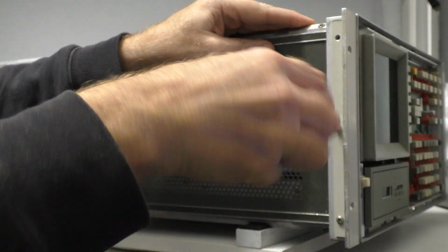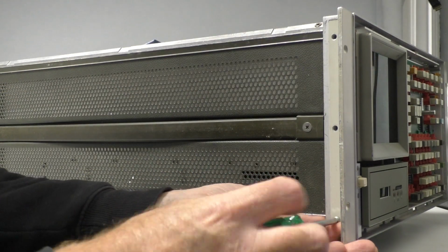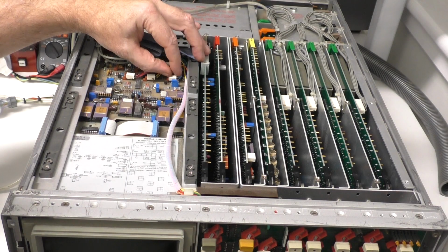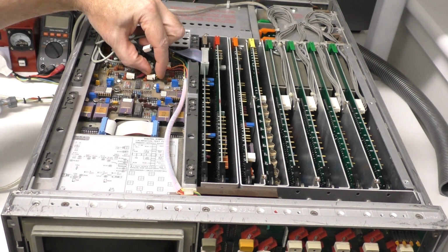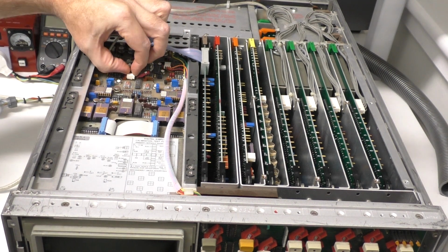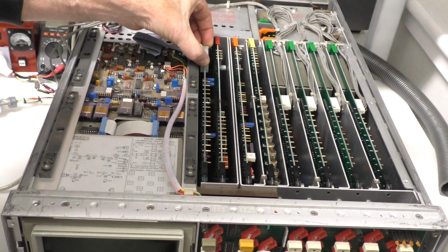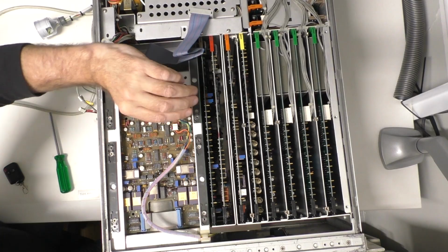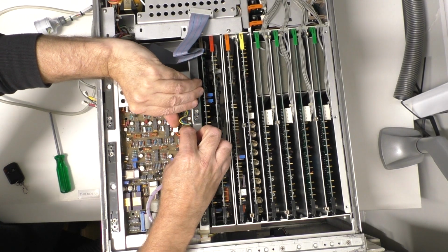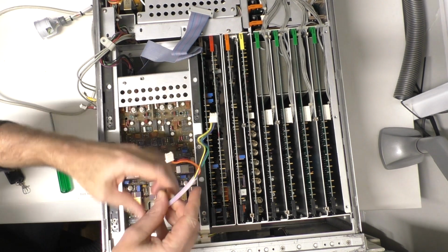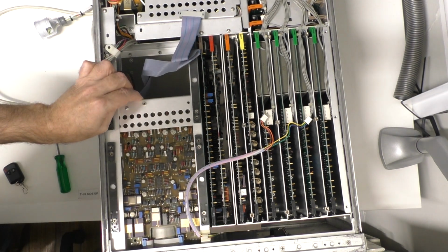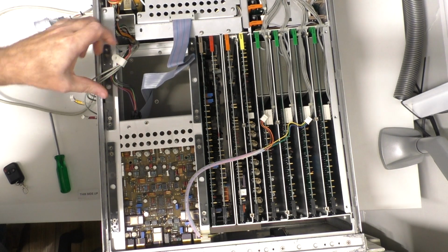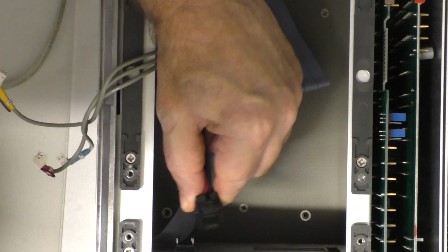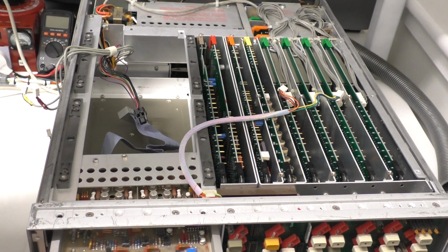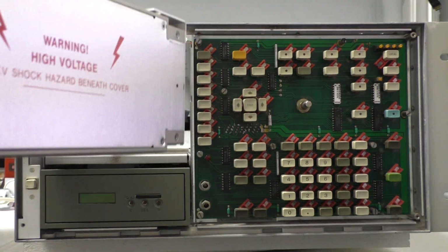Remove the left rack bracket and side screws from the unit. Unplug the XYZ cables from the display unit. Unplug the ribbon cable from the A1 graphics display control board assembly. Unplug the intensity and focus control cables from the display unit. Slide the display unit forward. Unplug the power connector. Remove the display unit and place beside the main unit.